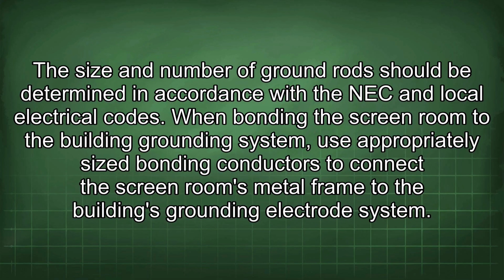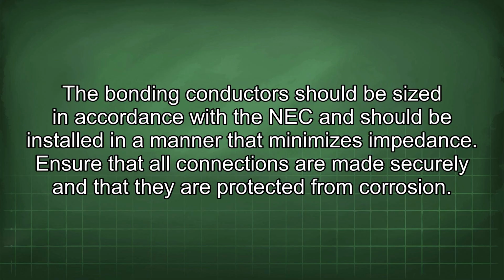When bonding the screen room to the building grounding system, use appropriately sized bonding conductors to connect the screen room's metal frame to the building's grounding electrode system. The bonding conductors should be sized in accordance with the NEC and should be installed in a manner that minimizes impedance. Ensure that all connections are made securely and that they are protected from corrosion.